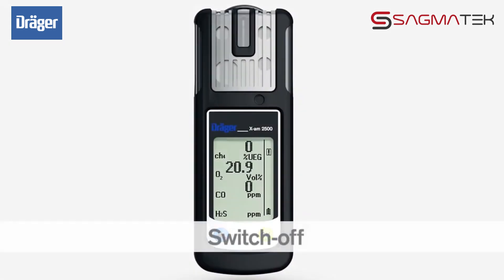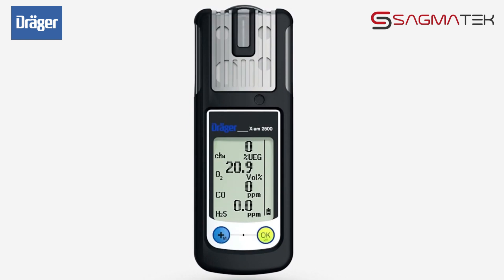To switch off the Dräger X-am 2500, press and hold the OK key and the plus key together for three seconds. The visual alarm flashes and the audible alarm beeps to indicate that the shutdown sequence is complete.